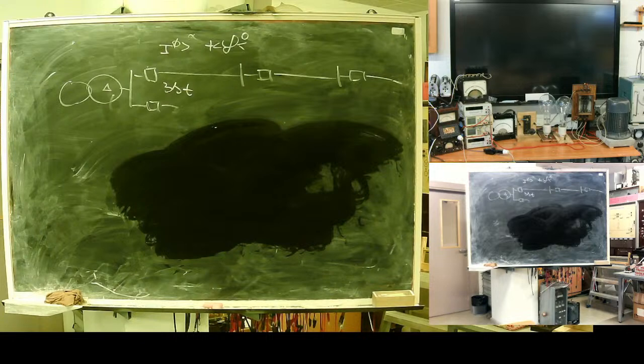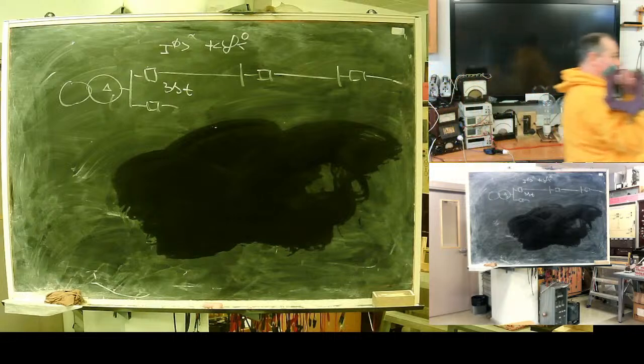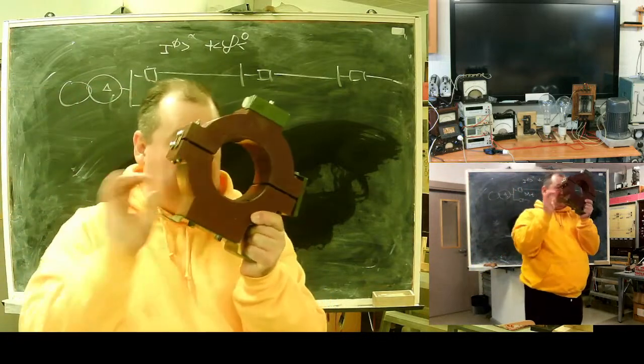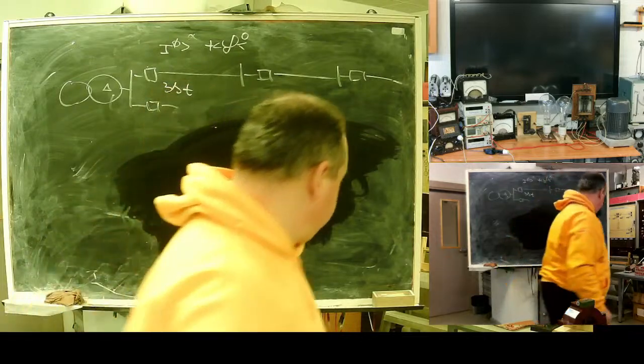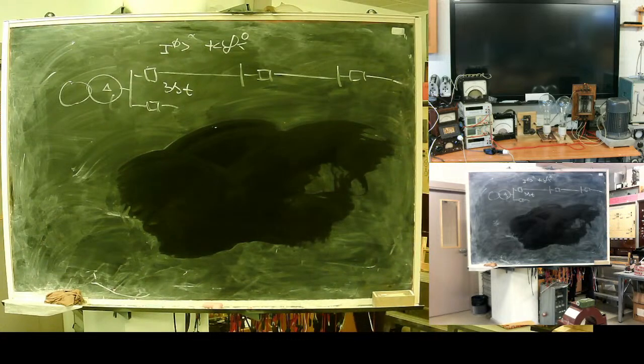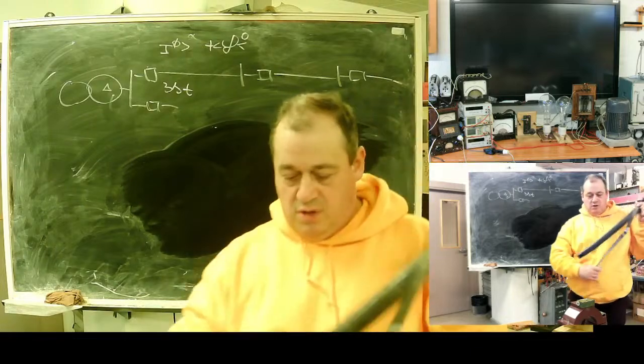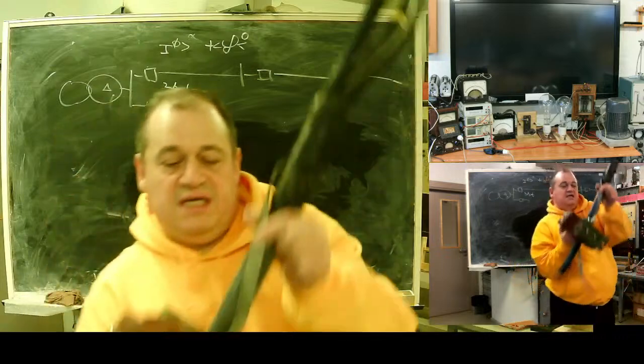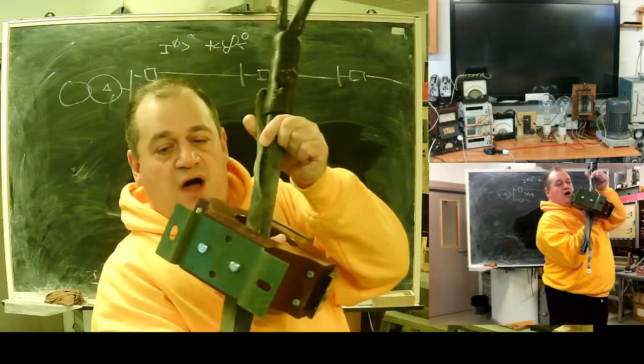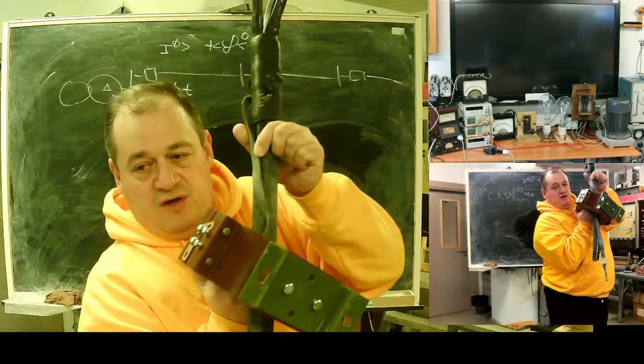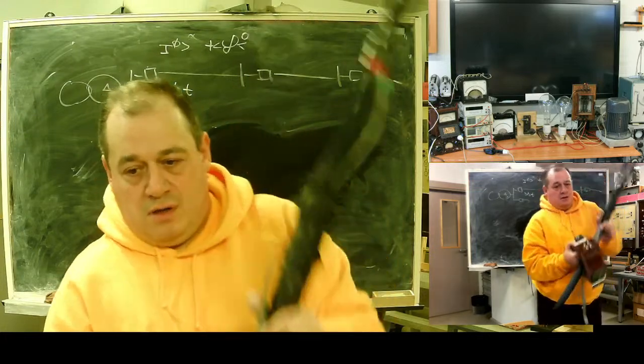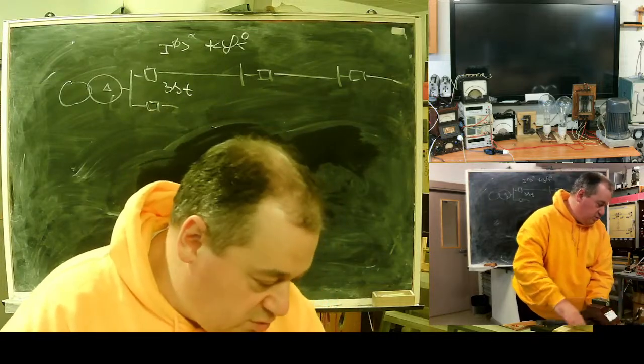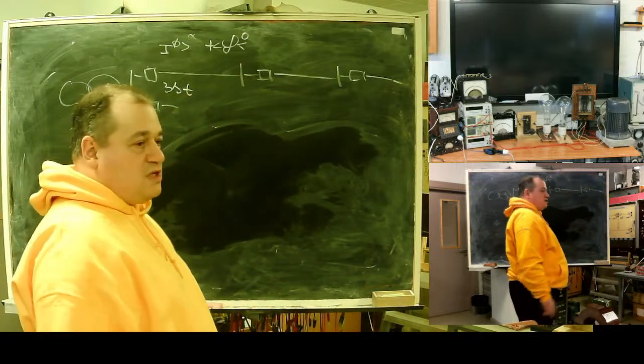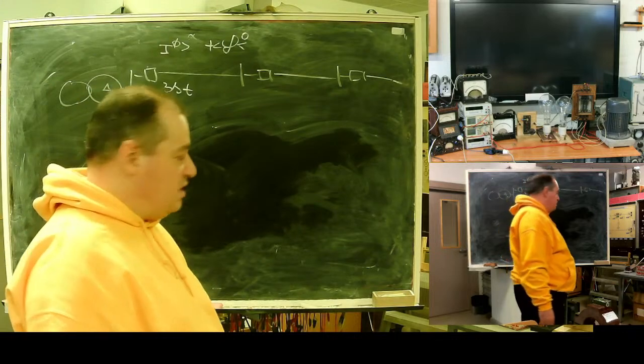Transformer. Here it is. Zero sequence transformer, or cable transformer. Cable. For example, the cable should go like this. The earthing screen wire should go back through the transformer to prevent self-operation from ground currents. Here it is. This is your source of zero sequence current. Do not try to use a phase transformer. Non-balanced current will ruin everything. You will have no sensitivity.